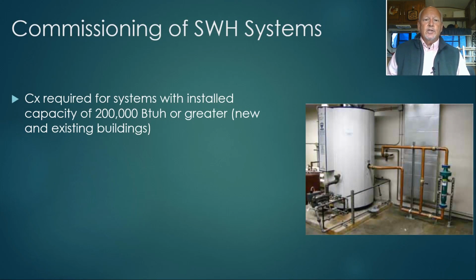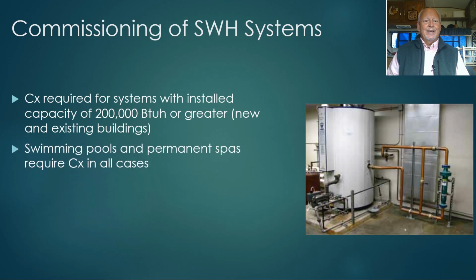And then finally, on service water heating commissioning. Commissioning is required for all service water heating systems with an installed capacity of 200,000 BTUH or greater. And this applies to both new and existing buildings. So if you're replacing a service water heating system in an existing building and the capacity is greater than 200,000 BTU, commissioning is required. What is in the scope of the commissioning?